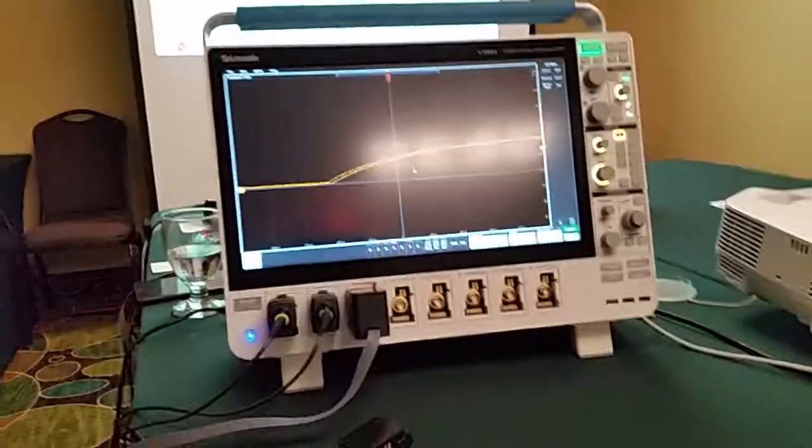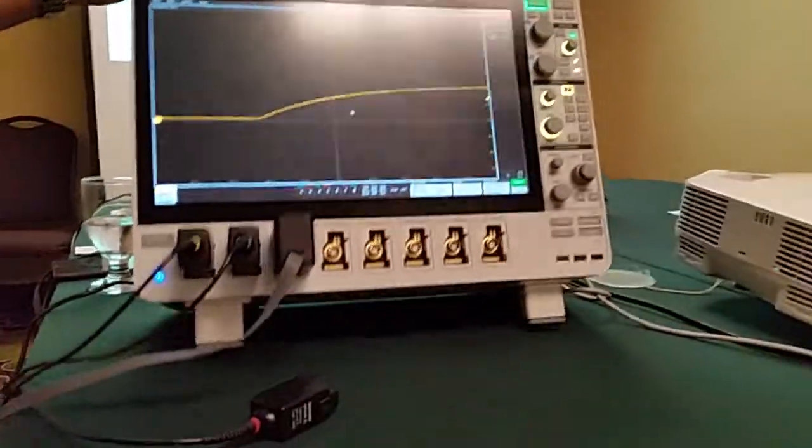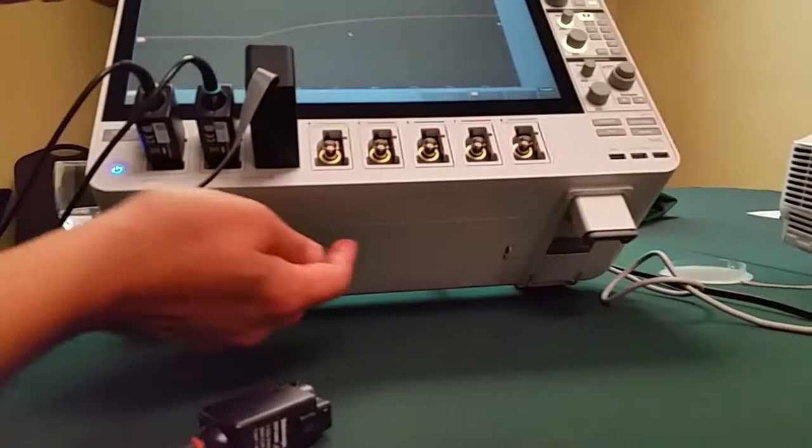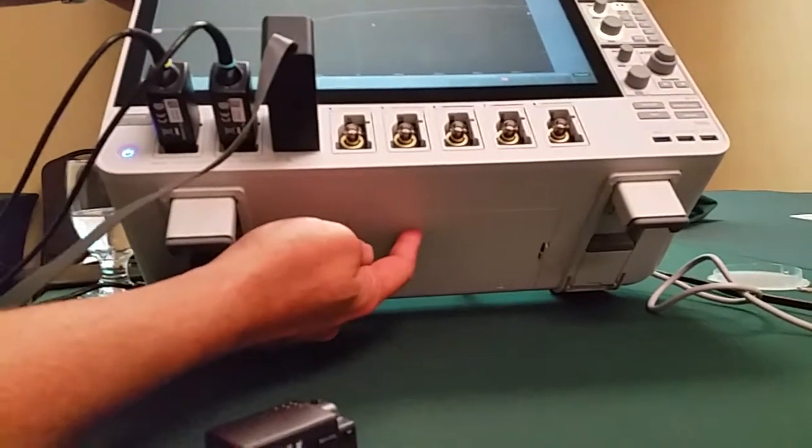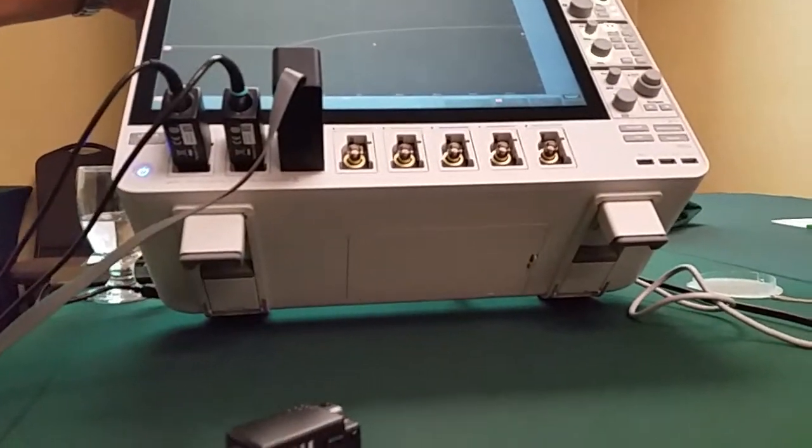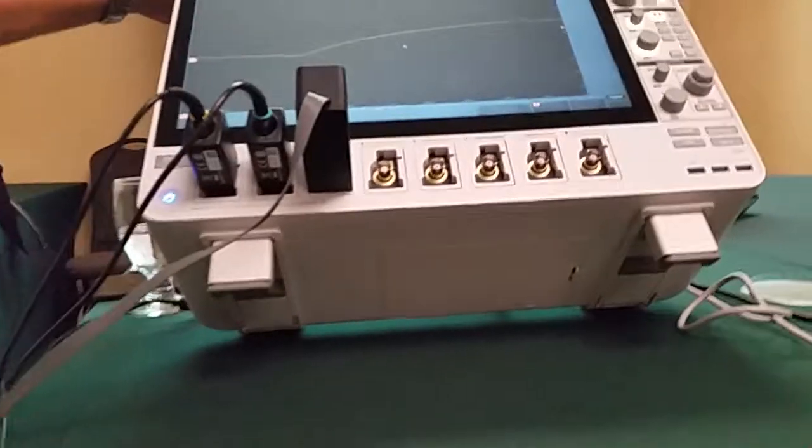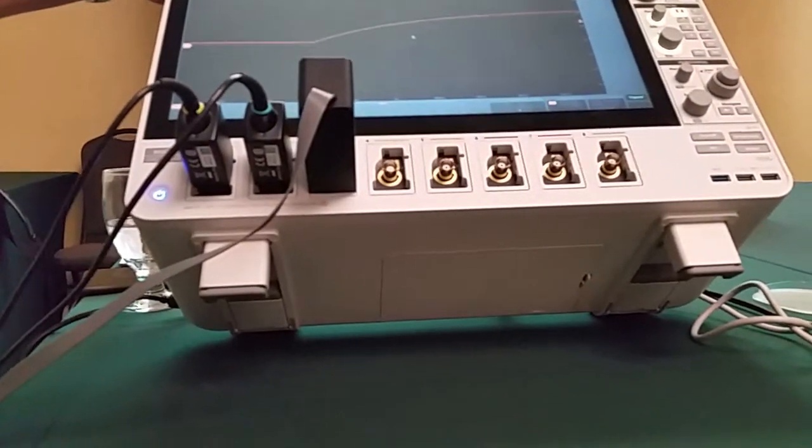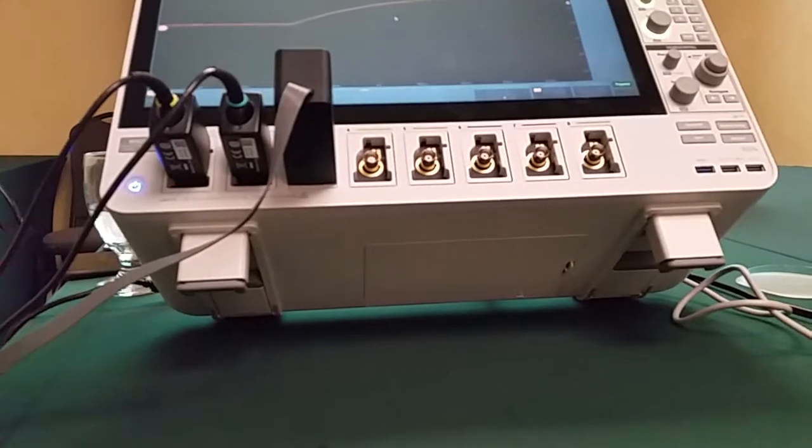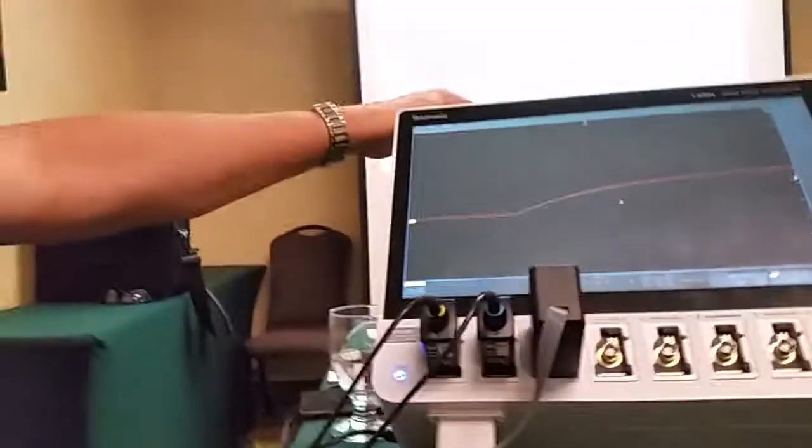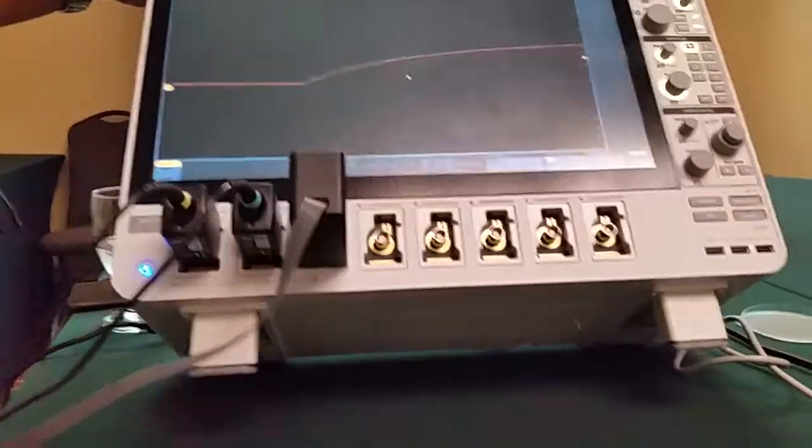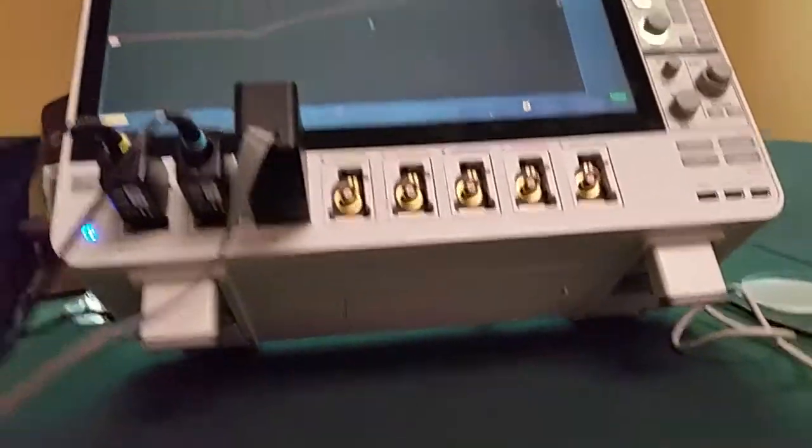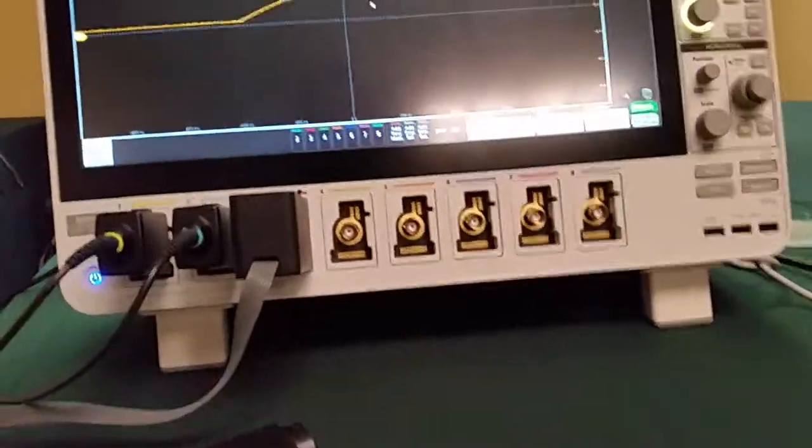How do you add the Windows operating system? So, if you look down here on the bottom of the instrument, there is an access panel, and behind that, there's a solid state drive with a Windows license and operating system, and if that's present, then the instrument boots as open Windows and you can install other applications and software on it. If that drive's not present, it boots as a dedicated scope.